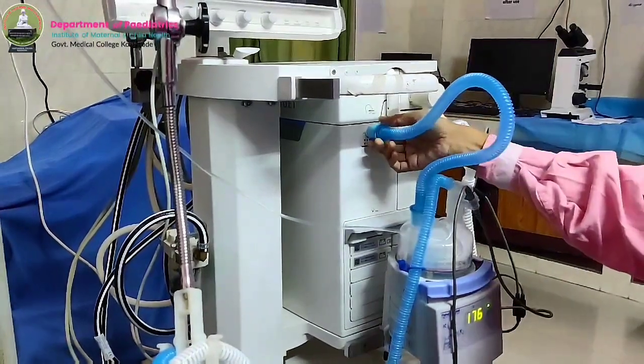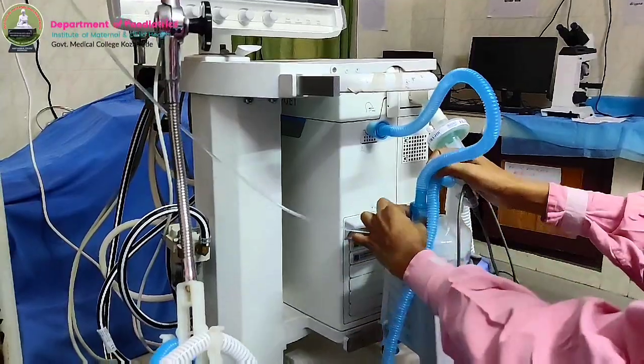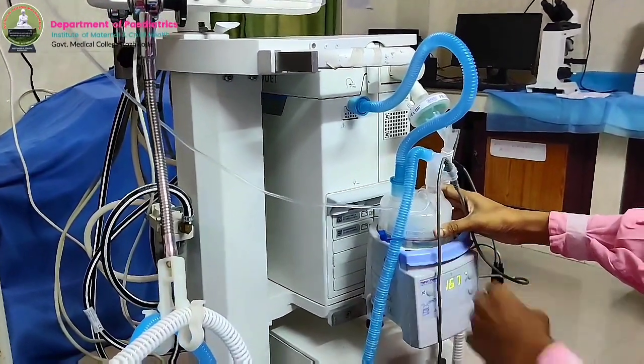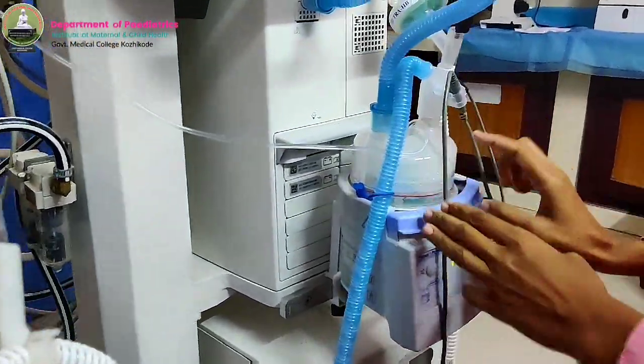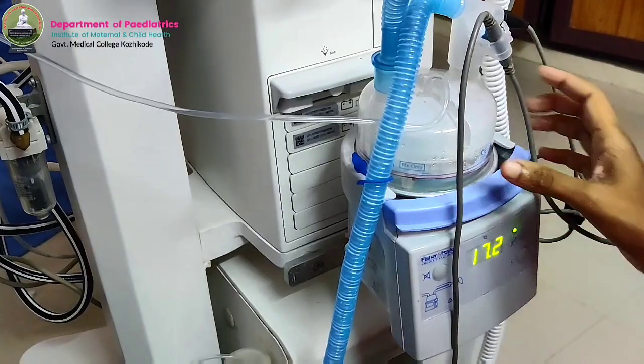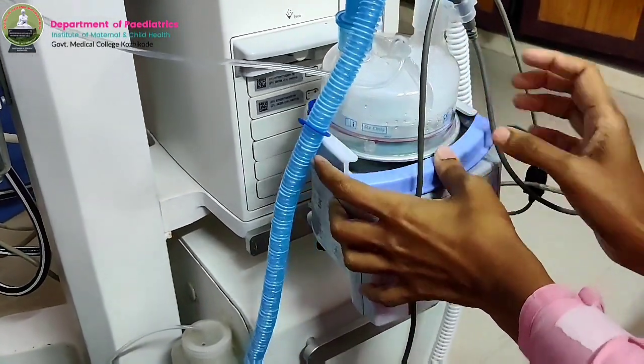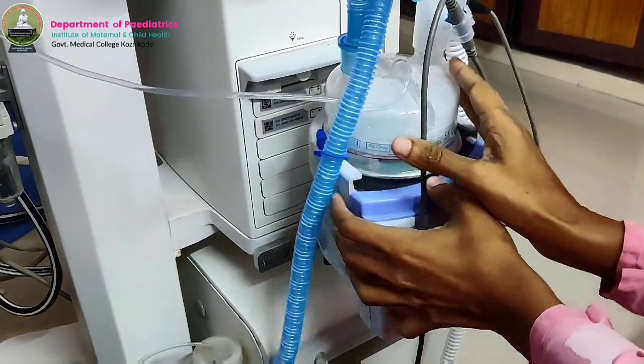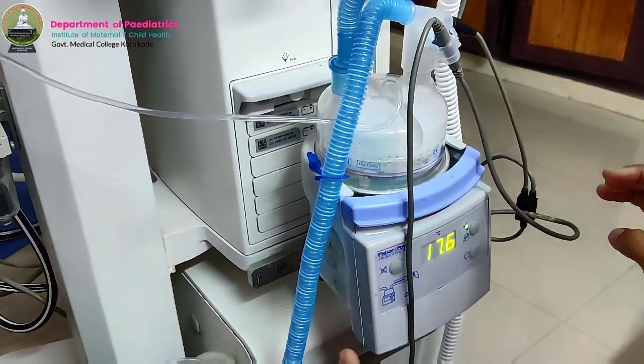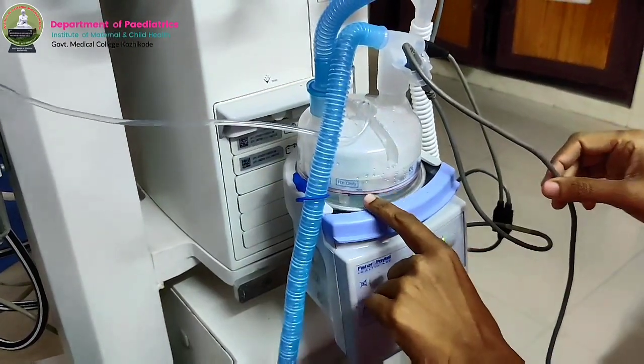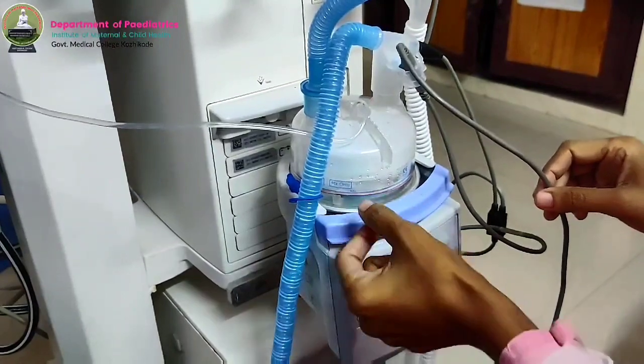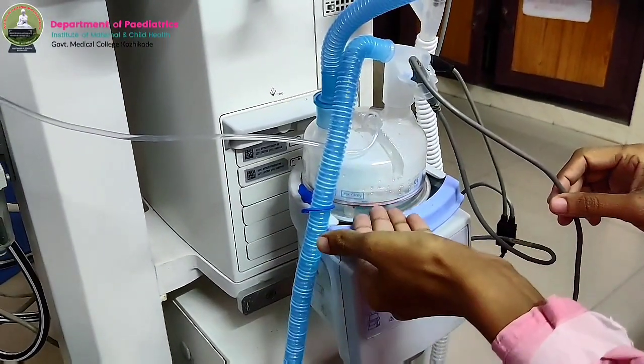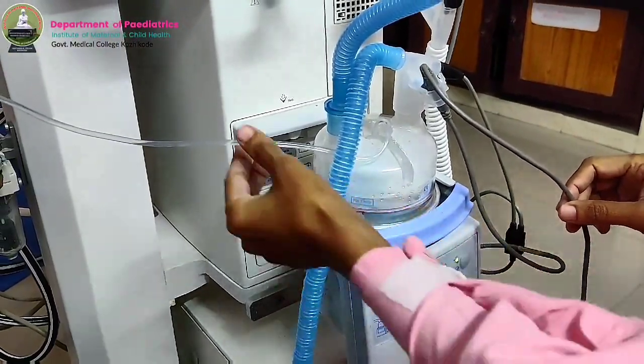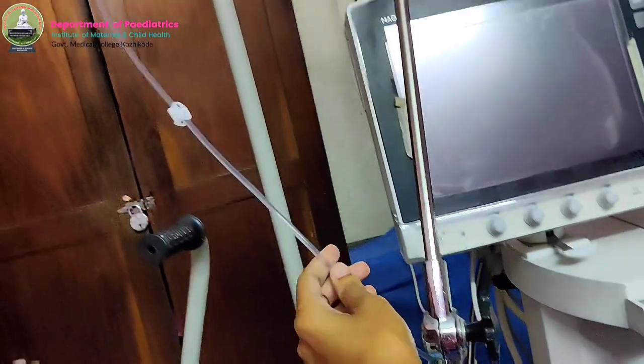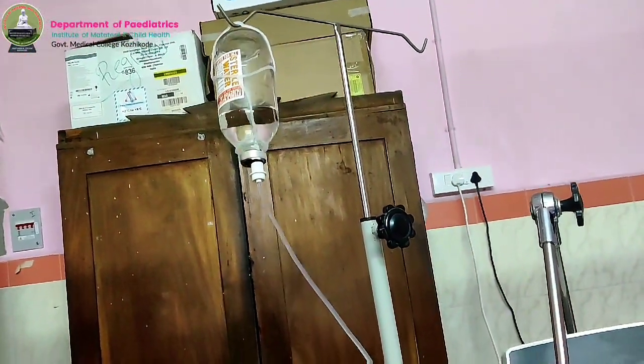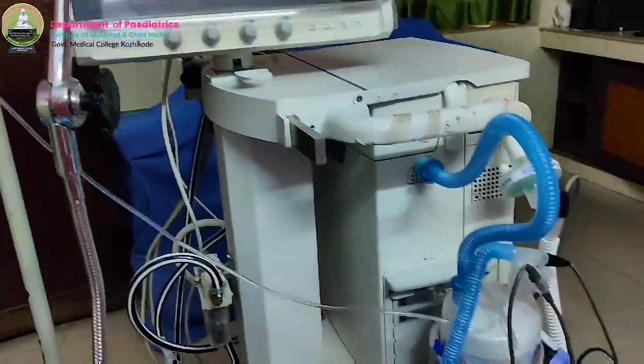We have a small segment connecting from this to the humidifier. This is the first connection. Then there is a disposable ventilator humidifier chamber. This is the humidifier chamber that can be slid in by pressing this blue part down. So this can be slid in and out. Keep it properly and add water up to the 2 blue lines in this chamber. There is a floating red material that will come in between the 2 blue lines. Up to that we should fill sterile water by a connection which is connected to the sterile water bottle. By operating this lock, we can add enough water as we need.